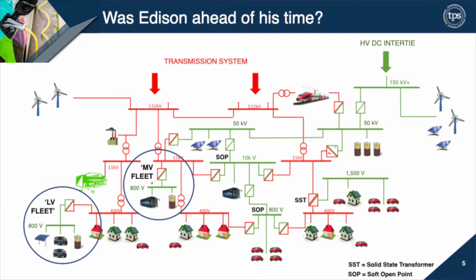We can start by putting what we call soft open points in the network. Soft open points connect different feeders together, allowing us to exchange electricity east to west or west to east. Why do I want to do that? I might have one overloaded feeder, and I might need to relieve it by introducing capacity from a feeder that's underloaded.